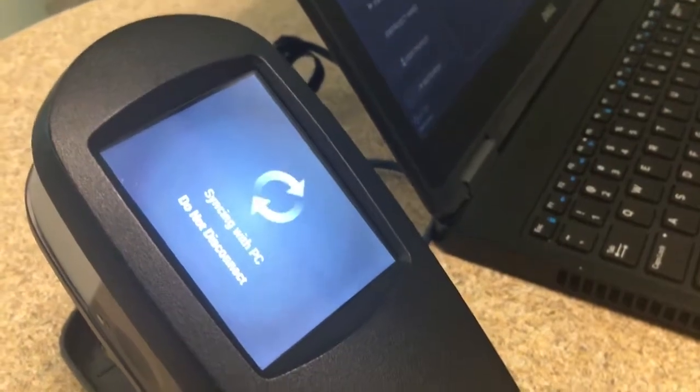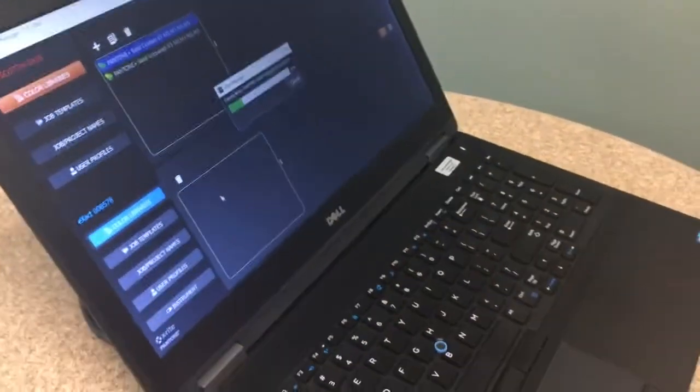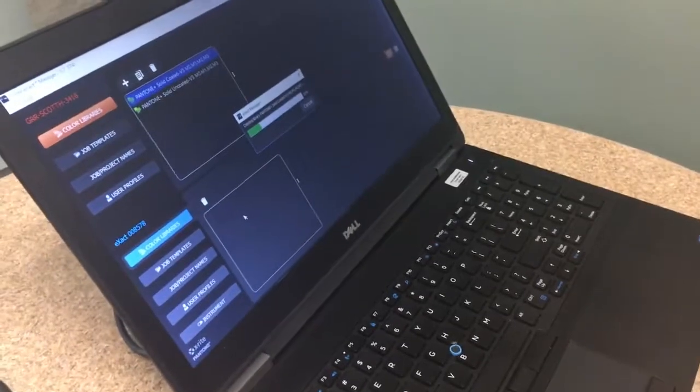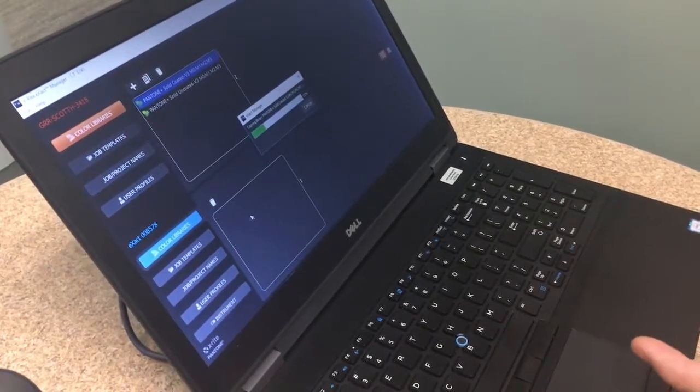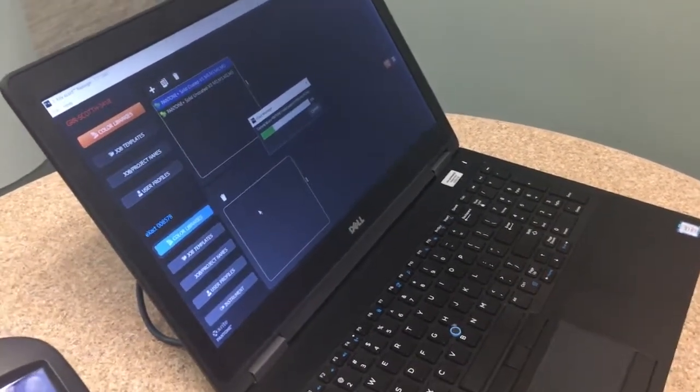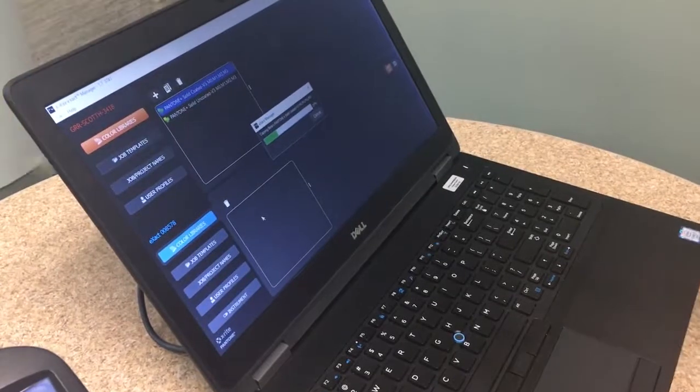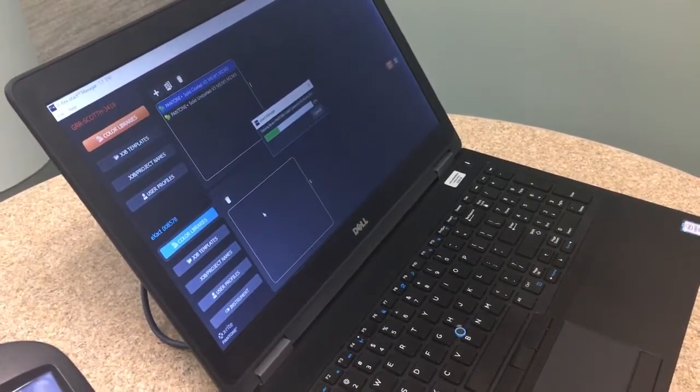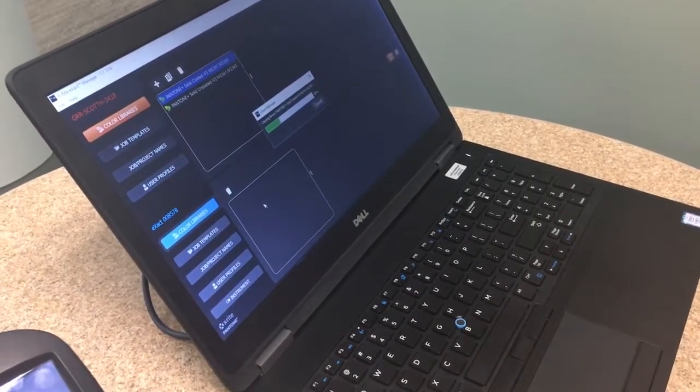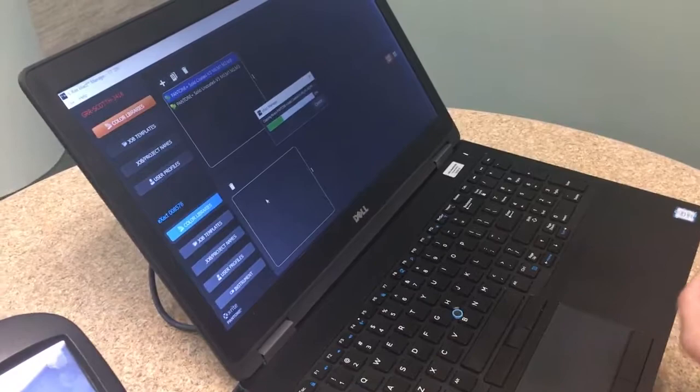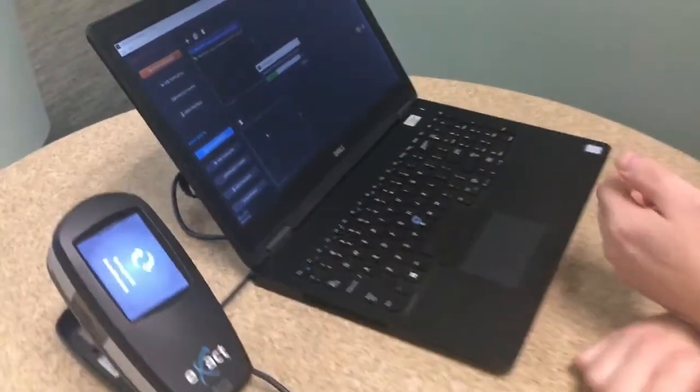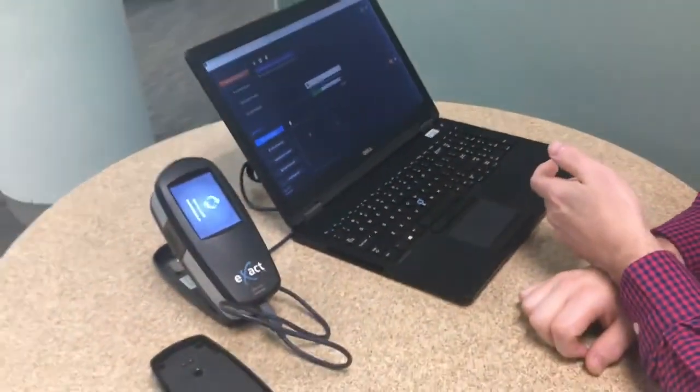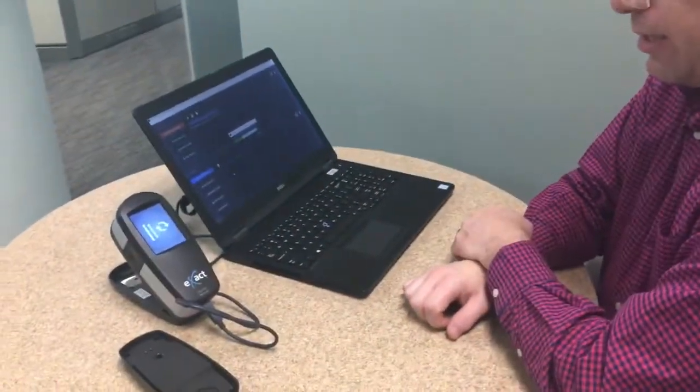Fantastic. And what other pieces of software does X-Act connect with? Well it comes standard with X-Act Manager. That's what comes with it and it's free. The other software program that comes with it is something called Data Catcher. That is a utility that you can connect to the instrument so you can take readings and put them into like an Excel spreadsheet or something else like that.